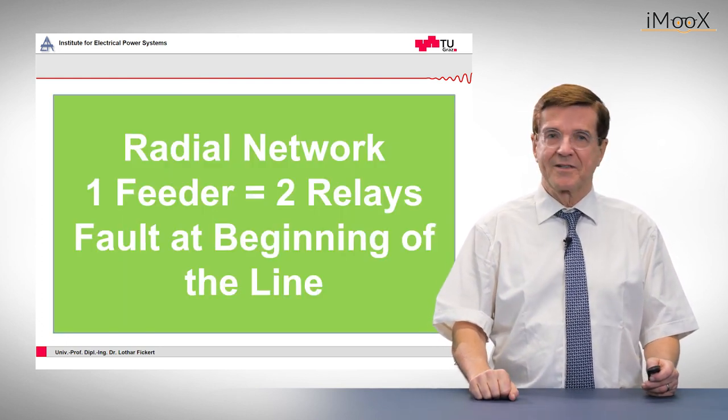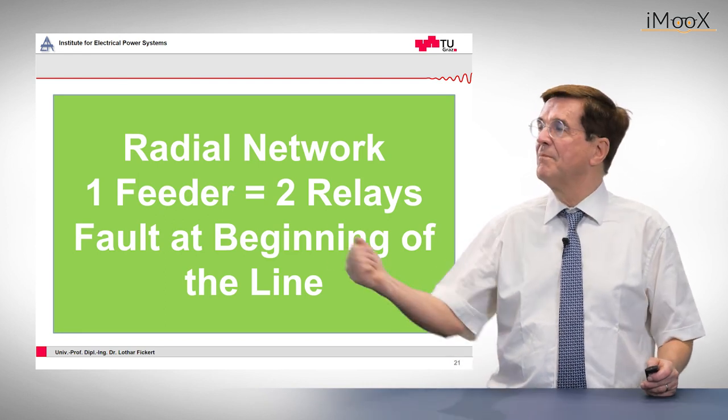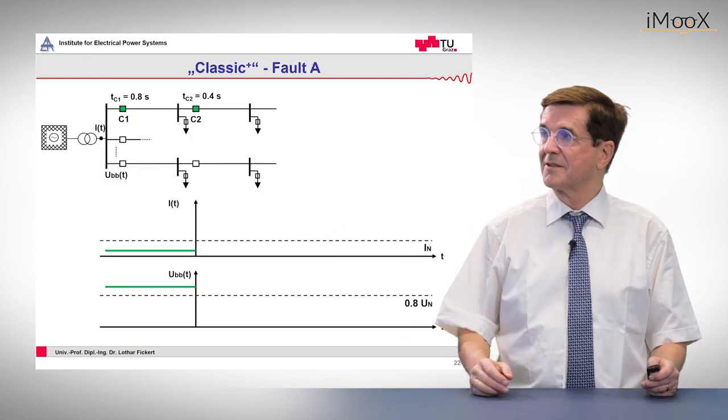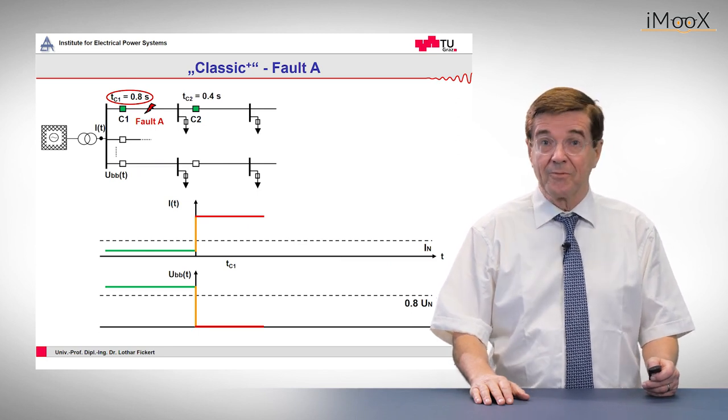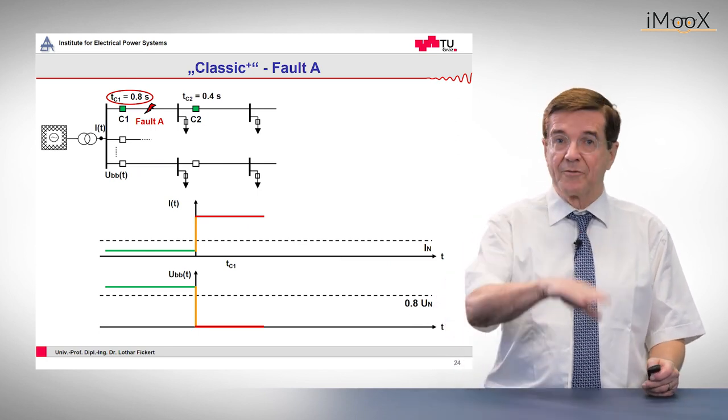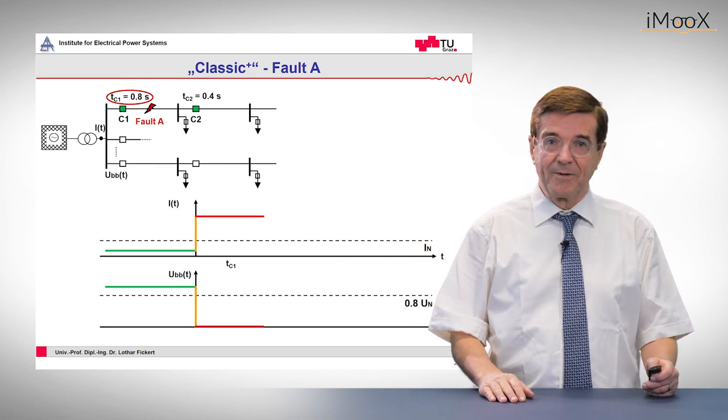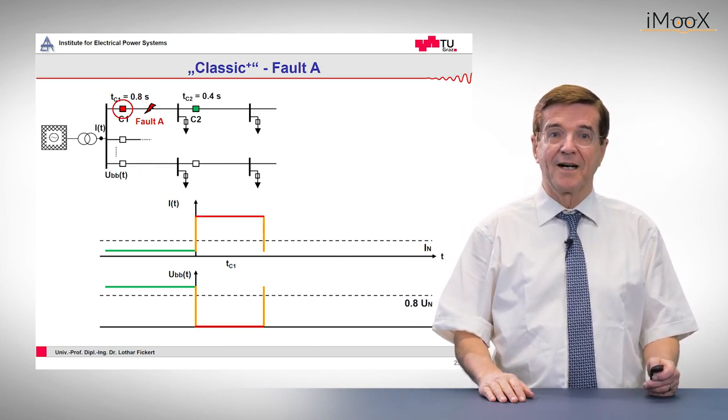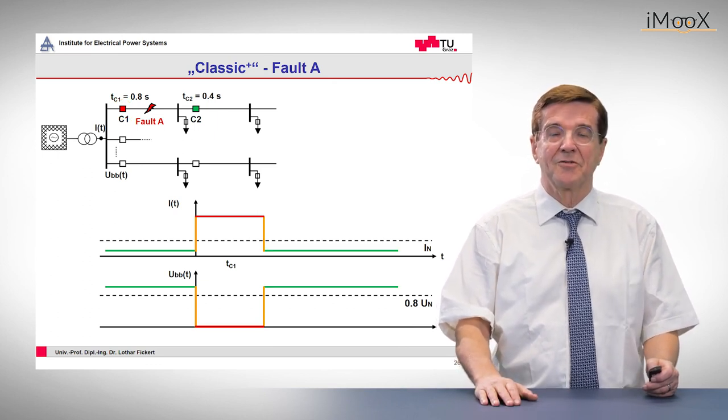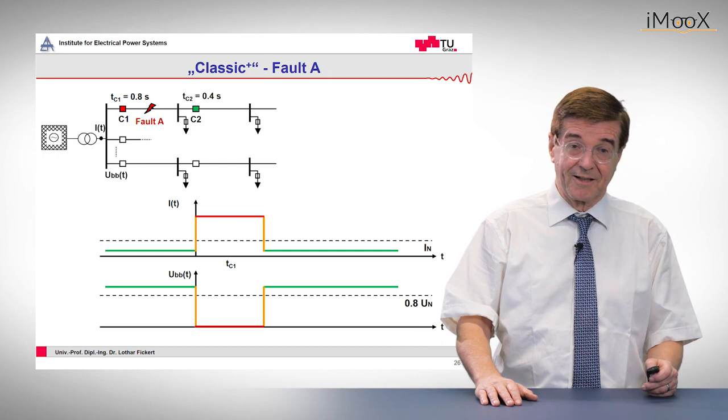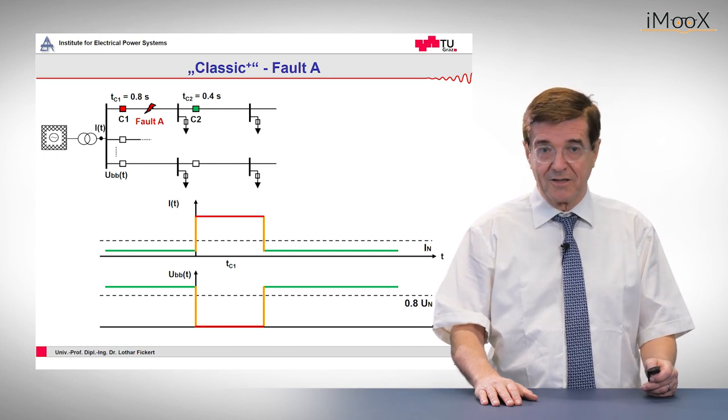What happens if we have the same network but now a fault at the beginning of the line? So again the fault occurs, the timer starts, but now we have, according to the principle of time grading, a higher tripping time of 0.8 seconds. After this, the circuit breaker opens and the whole system is at a regular voltage state at least. But one feeder is lost.